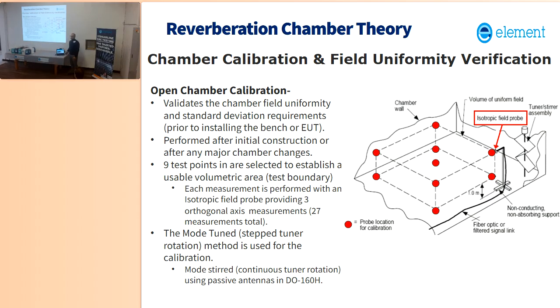Now, for your lab, any of the element labs, we do both because there's advantages to a calibration using the mode stirred method. Matter of fact, I've done this, and the field uniformity is much better when you do mode stirred. It's much better than the mode tuned with the E-field probes. So that's an option that's coming in DO-160H whenever that gets published. Hopefully, I don't know, I'm gonna say sometime next year. The people running the committee really want it to happen this year, but I don't think it's going to happen. There's just too many open issues.